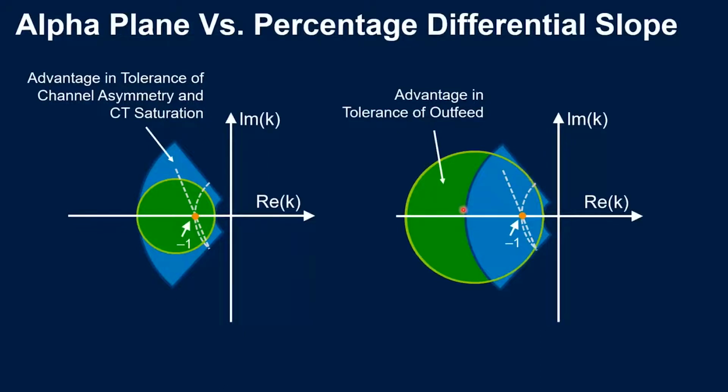But look at this. Remember the faults with outfeed that can be here? In this system on the right, if we have a fault with outfeed, it may not be seen by the traditional characteristic. So this is telling us about the compromise we have to make when choosing the slope of the traditional characteristic between these two or three scenarios. Okay.